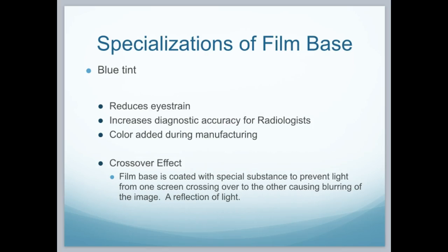The reason for the blue tint is it reduces eye strain to the radiologists, and in doing so it increases diagnostic accuracy. You can imagine 8 to 12 hours a day reading films — this blue tint really helped to take the edge off. It's added during the manufacturing process. Another benefit to this tint is crossover control — the film base is coated with a special substance to prevent the light from one screen crossing over to the other, causing blurring of the image.